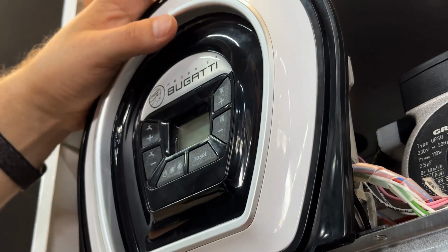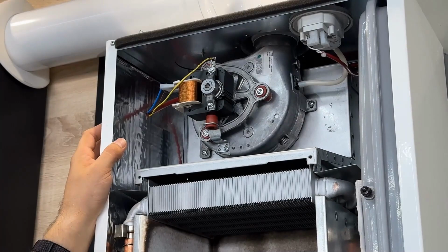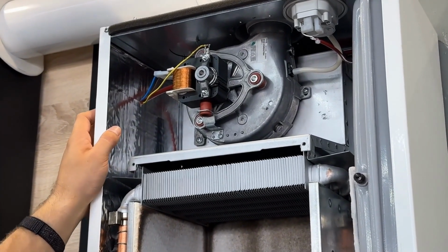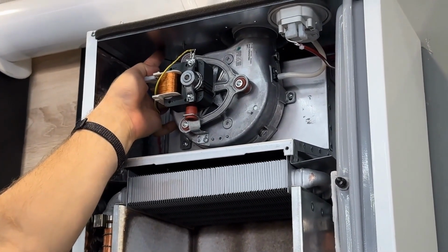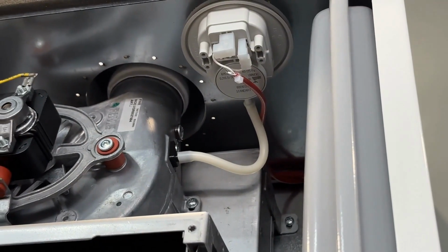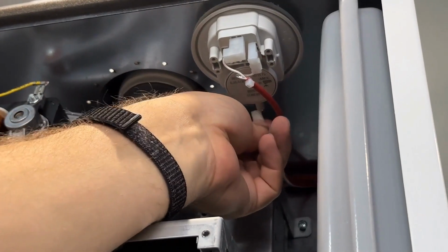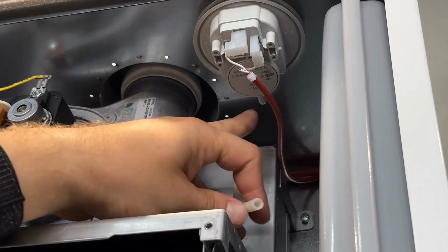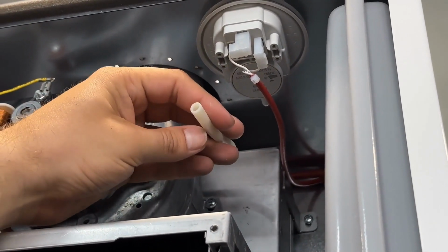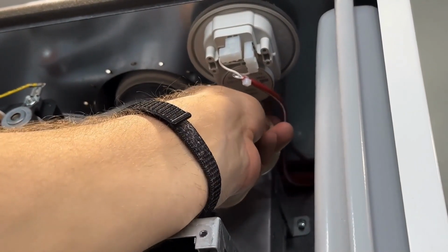To begin with, it is necessary to use heating temperatures above 50 degrees. Secondly, to dry the volume of the boiler, you can use the airflow from the room. To do this, you need to open the purge hatch. If condensate has formed in the impulse tube, we can blow it out. To do this, disconnect it from the pressure switch, making sure to remember which fitting it was connected to, blow out the tube, and reconnect it to the pressure switch.